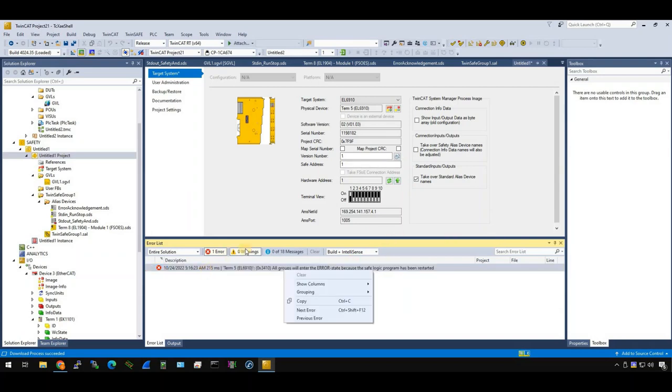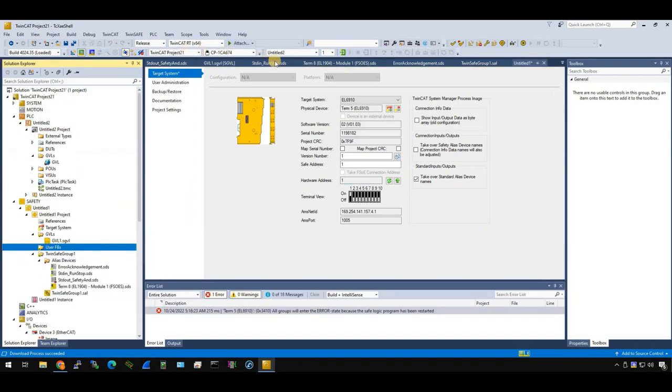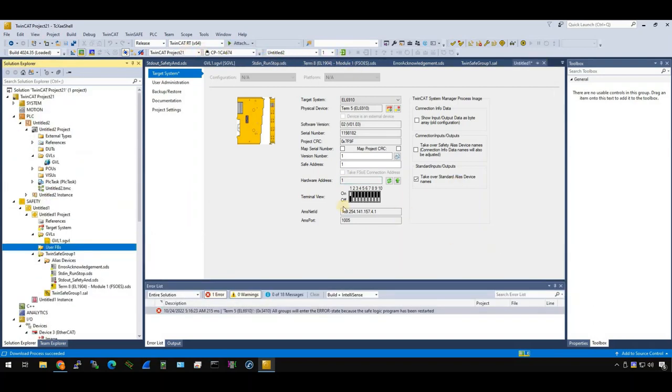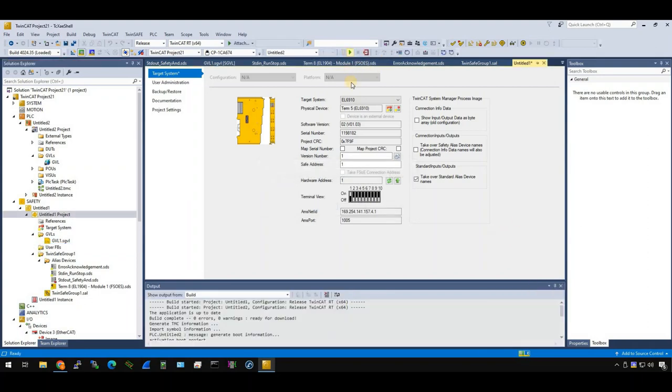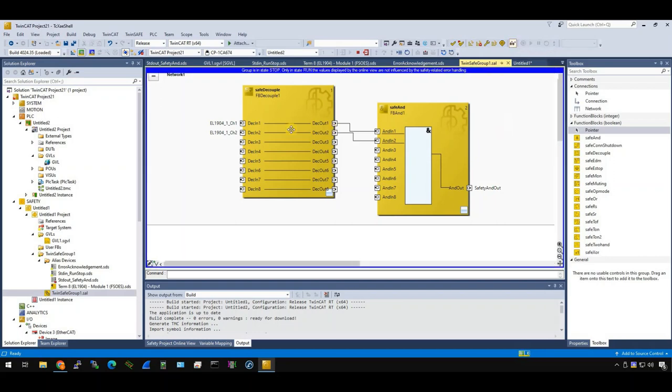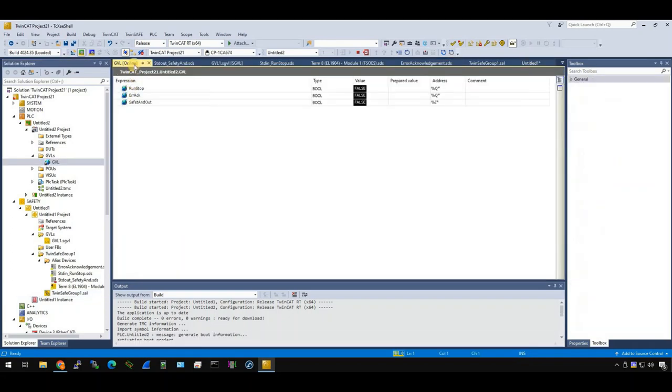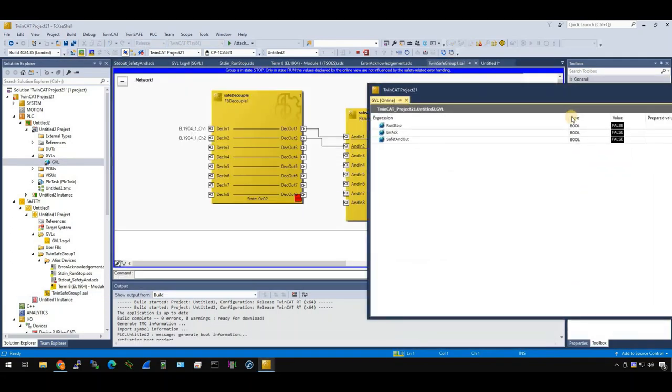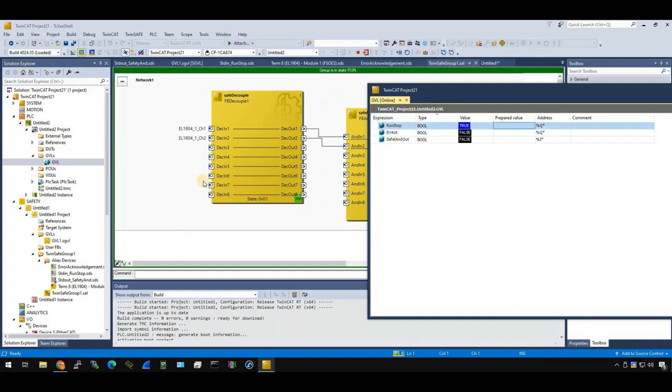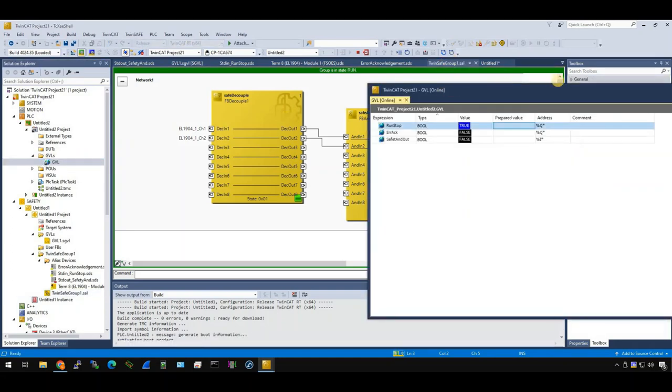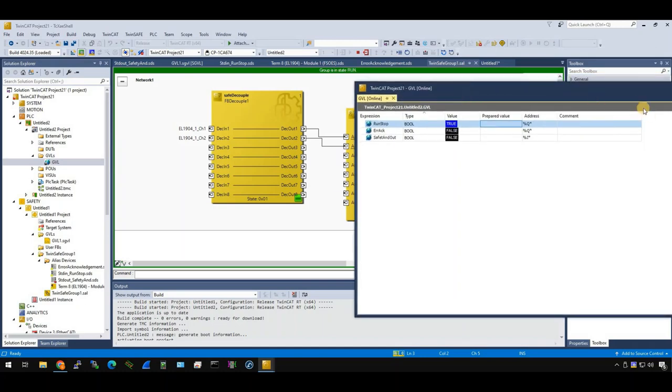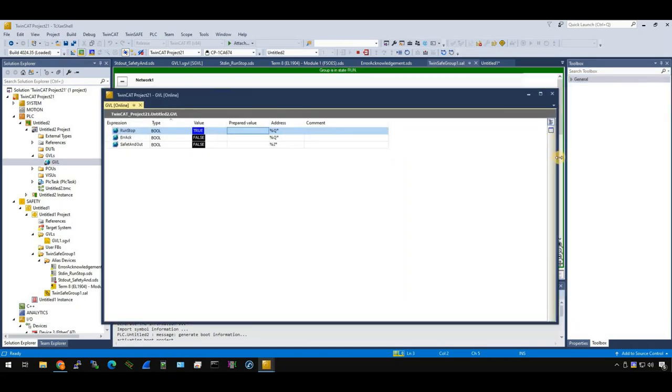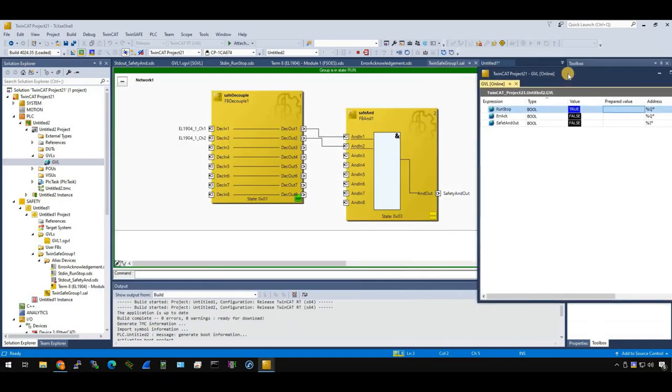Okay here. Things are okay, let the log in it. Let the system run and open our TwinSafe groups. And here is a glass icon, click here. Okay, now you can see this group is in blue. The message is reminding you that the group now is in stop status, you need to trigger it. So what can we do? Let's open the GVLs and go here to trigger this run_stop flag. Good, now you can see the group is in run status. And now you see there's no output, right? Just let me adjust it a bit, easy to see. Wait a second, I would like to show you the whole result in the standard PLC and also the safety project.